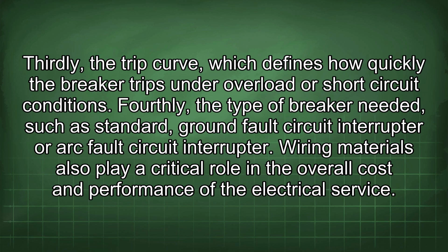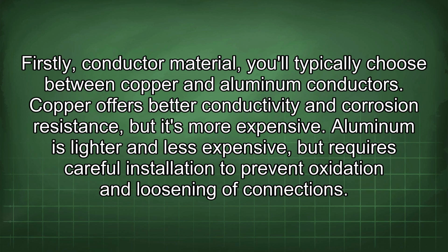Wiring materials also play a critical role in the overall cost and performance of the electrical service. Firstly, conductor material. You'll typically choose between copper and aluminum conductors. Copper offers better conductivity and corrosion resistance, but is more expensive. Aluminum is lighter and less expensive, but requires careful installation to prevent oxidation and loosening of connections.